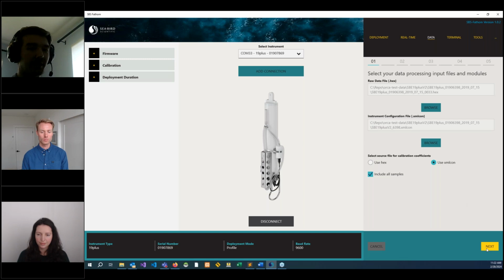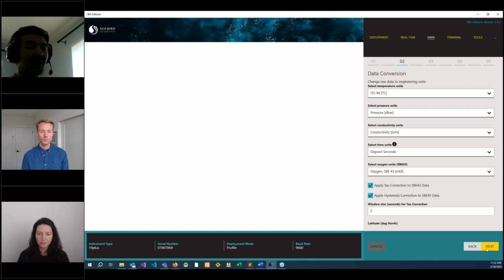The other benefit to loading in your XMLCon file is, particularly for a 19 plus V2, if you have some auxiliary sensors attached like this one does, then you're going to need that XMLCon file to get some of those calibration coefficients for the auxiliary sensors.